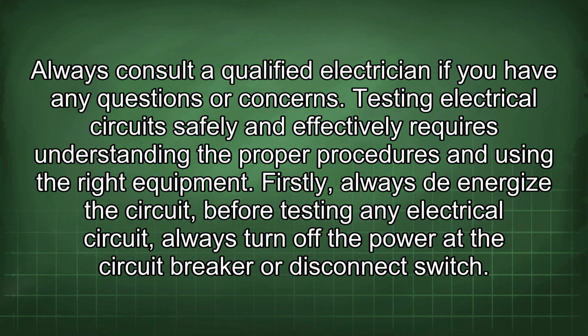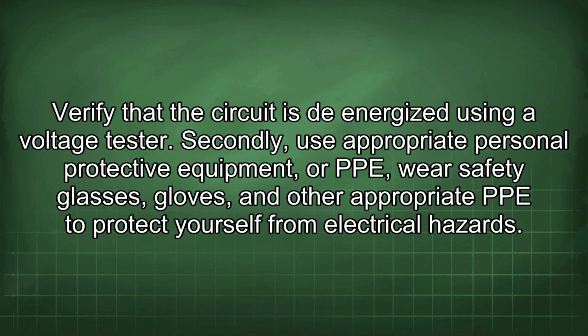Testing electrical circuits safely and effectively requires understanding the proper procedures and using the right equipment. Firstly, always de-energize the circuit. Before testing any electrical circuit, always turn off the power at the circuit breaker or disconnect switch. Verify that the circuit is de-energized using a voltage tester. Secondly, use appropriate personal protective equipment, or PPE. Wear safety glasses, gloves, and other appropriate PPE to protect yourself from electrical hazards.